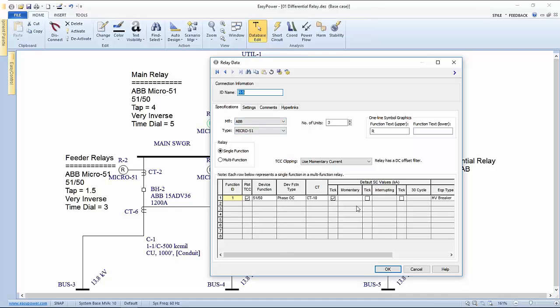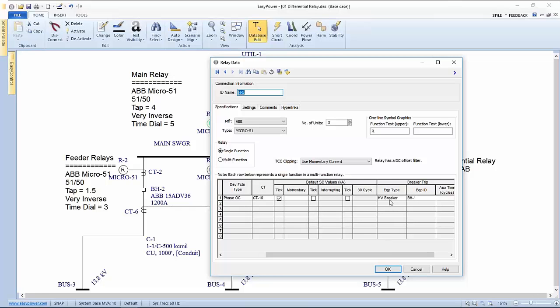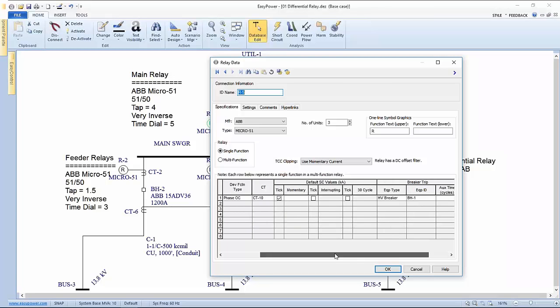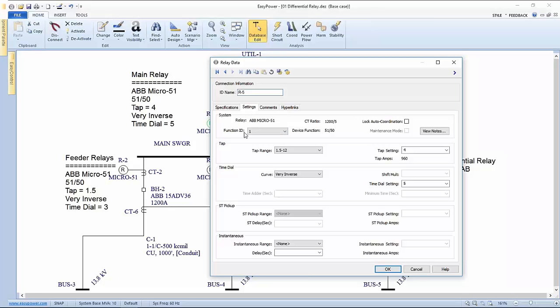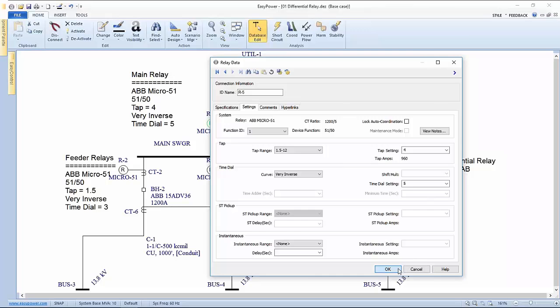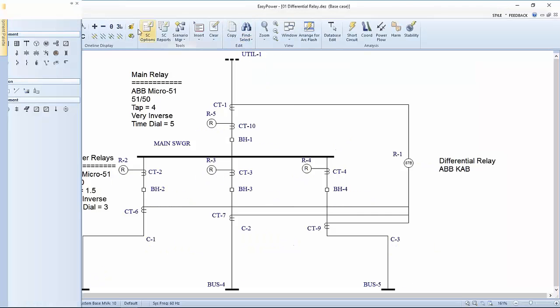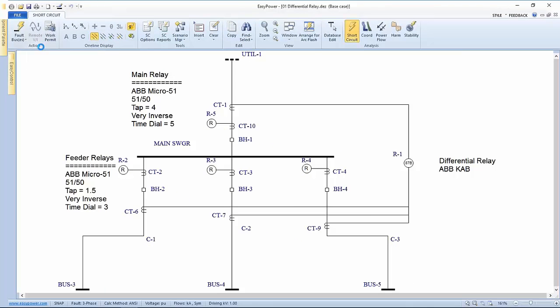This is all set up, if I open up this dialog box, based upon the fact that we have a specific relay from the manufacturer. In our settings, we're indicating this is a single function. In our arrangement, we're showing how it's tied to a specific breaker to trip, and that breaker may or may not have an operation time that we want to incorporate in our time delay. When we go to the settings tab, we then characterize the dial settings for that specific function. These are the values that we record as we do data collection on the trip device.